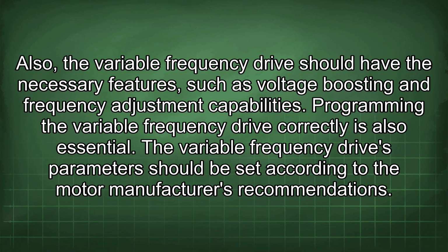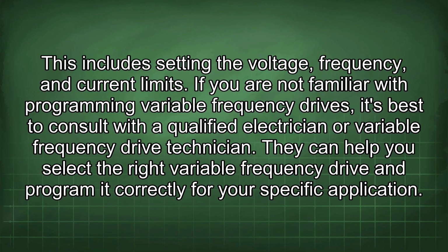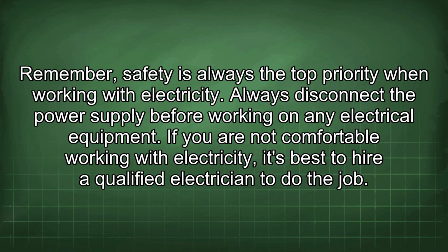Programming the variable frequency drive correctly is also essential. The variable frequency drive's parameters should be set according to the motor manufacturer's recommendations. This includes setting the voltage, frequency, and current limits. If you are not familiar with programming variable frequency drives, it's best to consult with a qualified electrician or variable frequency drive technician. They can help you select the right variable frequency drive and program it correctly for your specific application. Remember, safety is always the top priority when working with electricity.